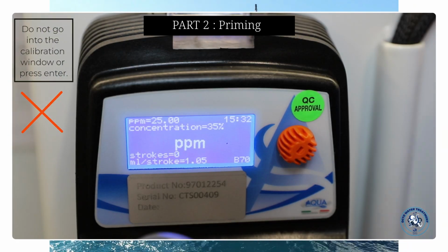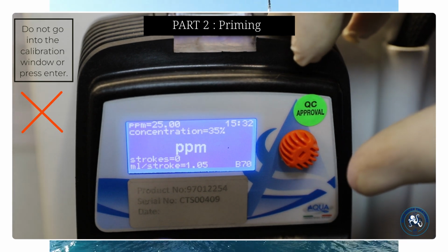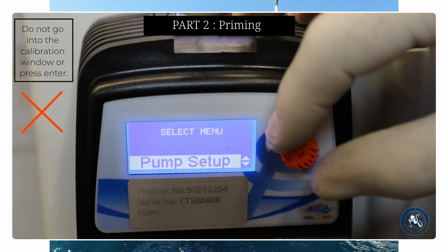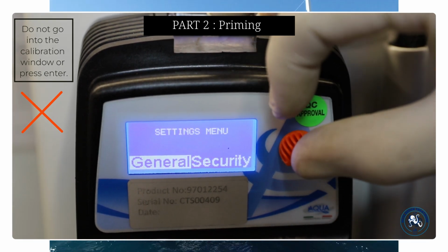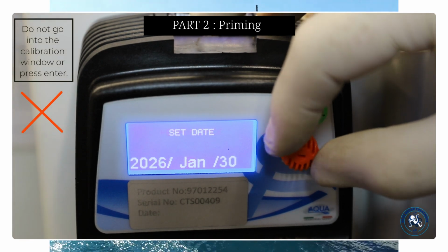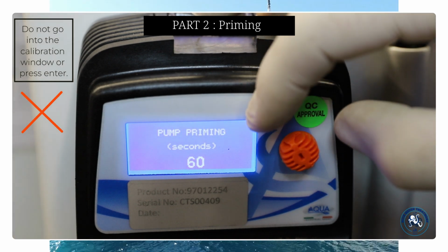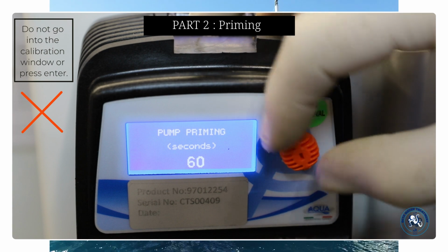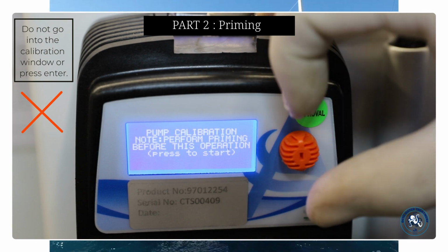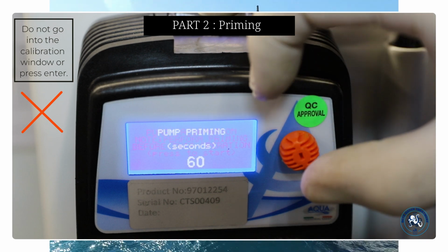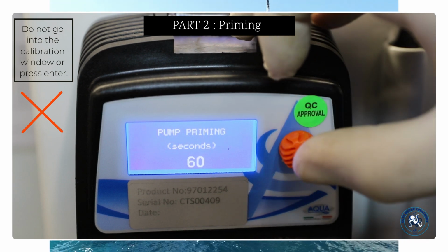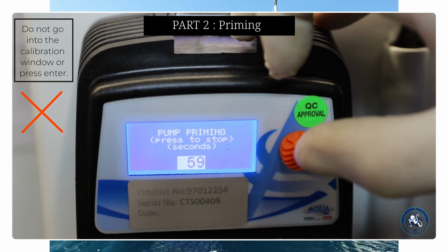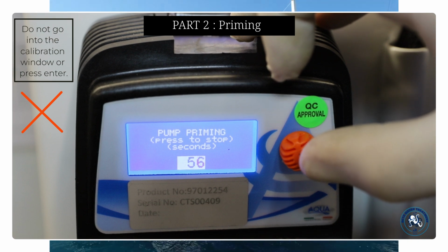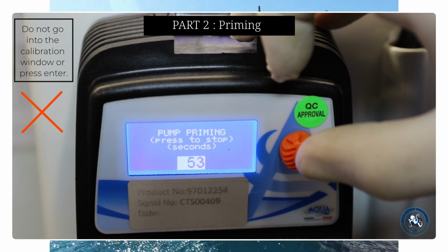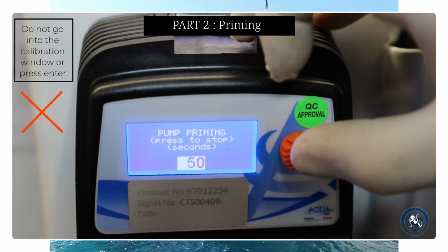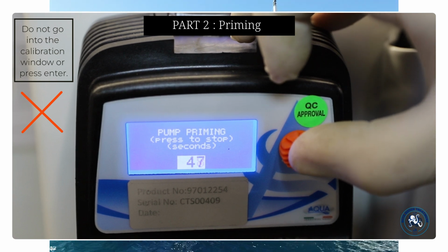Now we'll show you how to prime your pump. If your pump has not been used for approximately 1 week, proceed to priming, or if you are replacing the Hydrasil drum, also proceed to priming. It is very important you do not go into the calibration window on the screen and press the button, otherwise you will need to redo your settings all over again. Go to the pump priming window and press the button once to select and a second time to start the priming. The priming needs to be done to get rid of all the air bubbles to the injector. Once it's finished, hold down the button several times to return to the main menu.